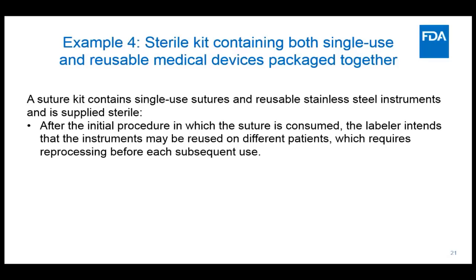So if we clarified it in the device description, we would not have to necessarily match the UDI of the package where it's bundled together to be the same UDI on these 2 individual. You wouldn't even be able to. That would be impossible. Okay, all right, thank you.